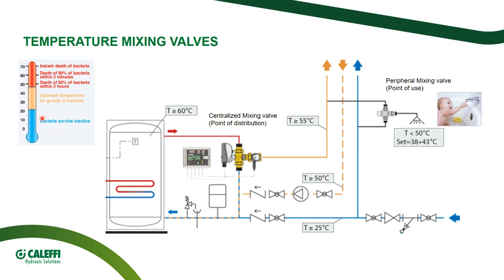The temperature range in between is an optimum environment for the Legionella spreading, and unfortunately, it is also the optimum interval for domestic water use. So our system has to manage this risk the best possible way and defeat the Legionella, if possible, everywhere through the system. That's why the storage is kept hot.